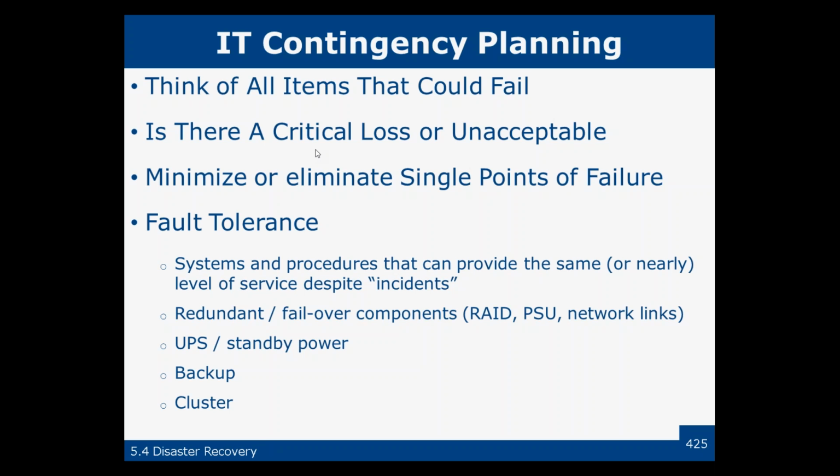UPSs and standby power. A UPS is not designed for long-term power supply. A UPS is typically going to last for a few minutes. They're designed to give you enough power to keep the systems running until the standby power, a standby generator maybe, comes online and takes the load.